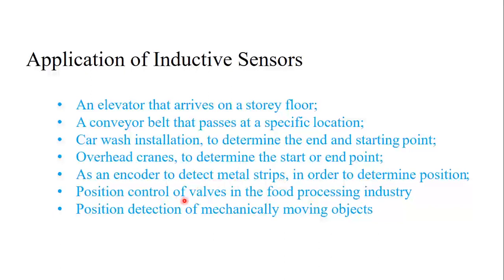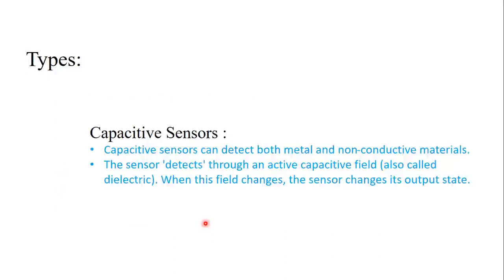Now let's move to capacitive sensors. Capacitive sensors can detect both metallic and non-conductive materials. Non-conductive materials include solids and liquids. The operation principle of the capacitive sensor is that it emits an electric field. If any object is nearby, this electric field undergoes changes, and these changes are detected by the capacitive sensor — that's how it operates.